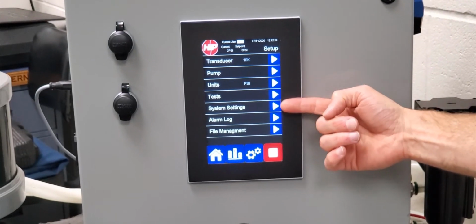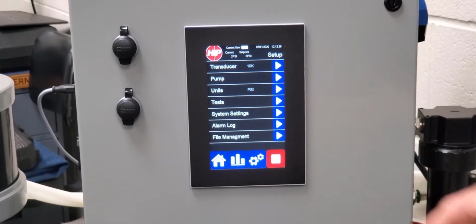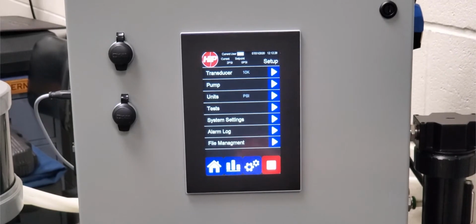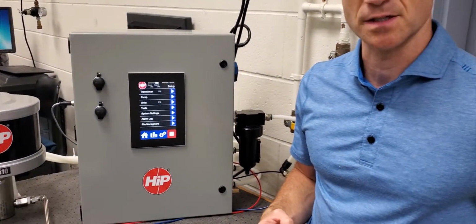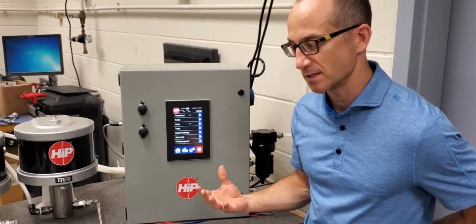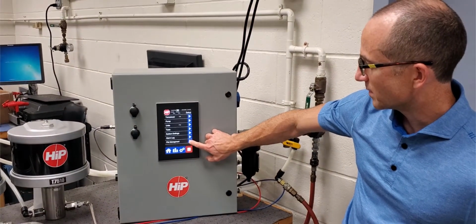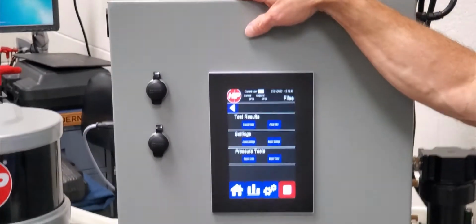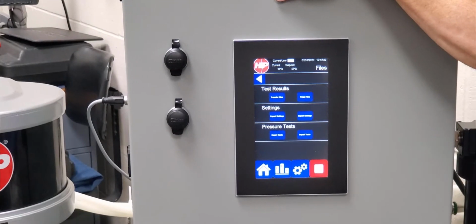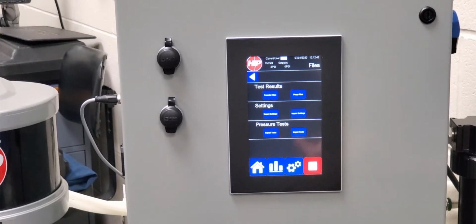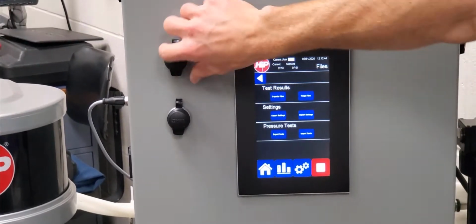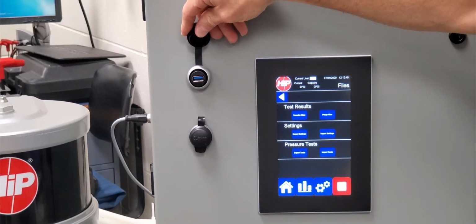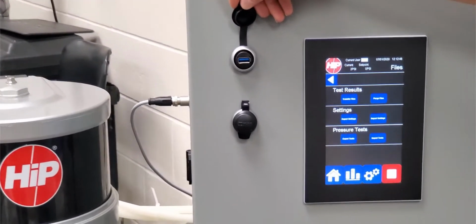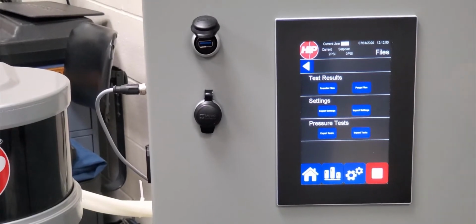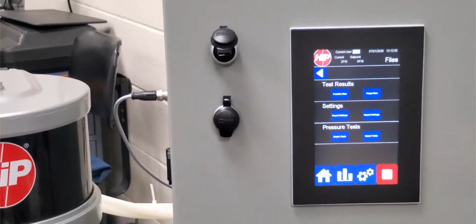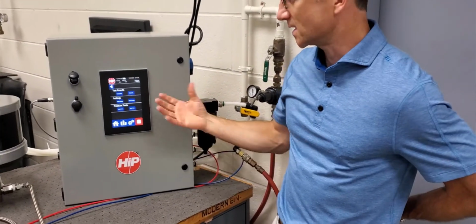Lastly, we have 3 parameters here. If you go into those, it'll dig deeper into global system settings that are a one-time set it and forget it type of feature. The last thing I want to mention is file management. Every time we run a test on this system, we're going to save a test report, and we're going to save that test data, and that can be downloaded via a USB port and provided to your customers. It also allows for preloading system settings or saving units in the case of software upgrades.